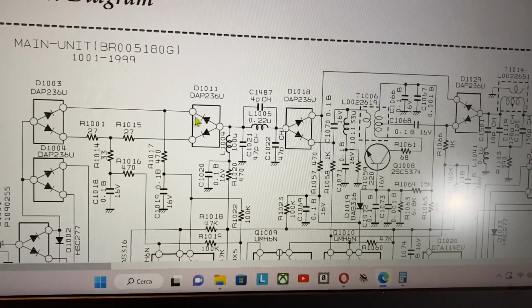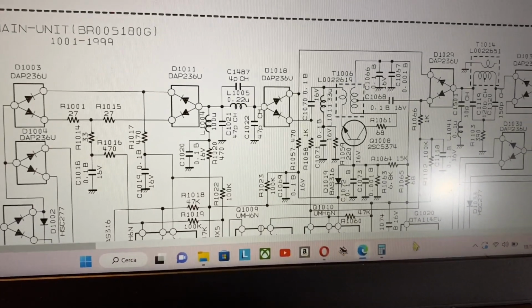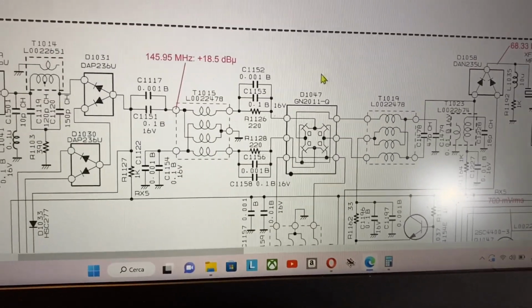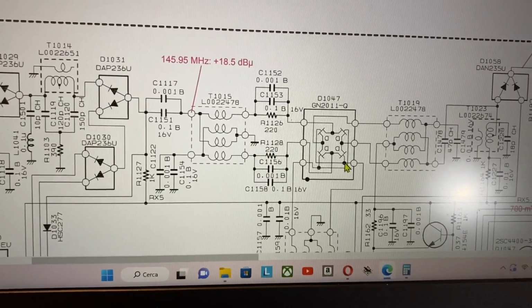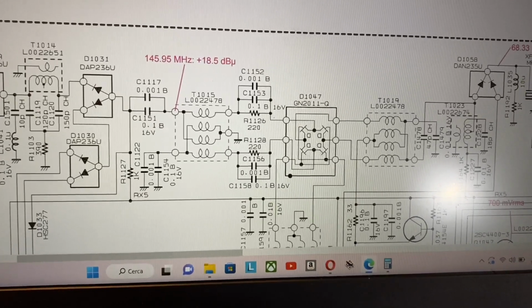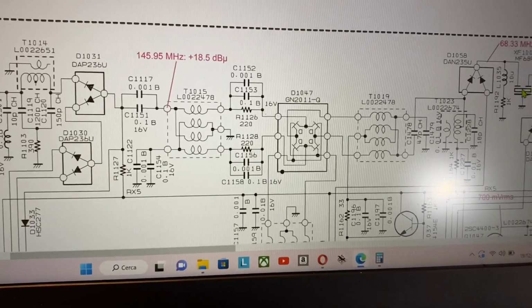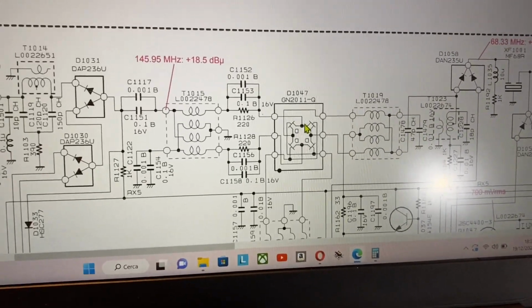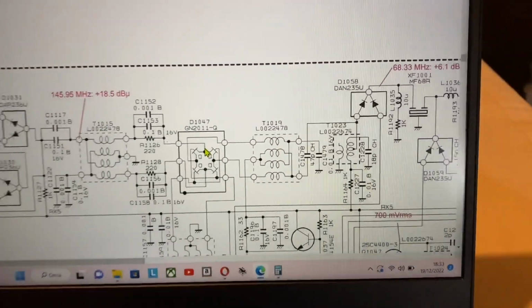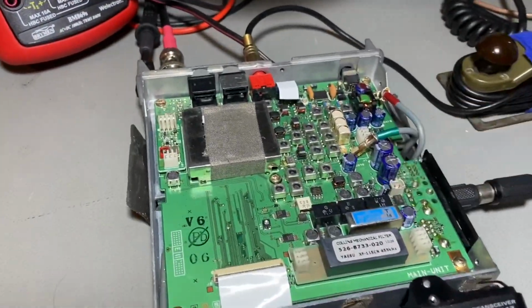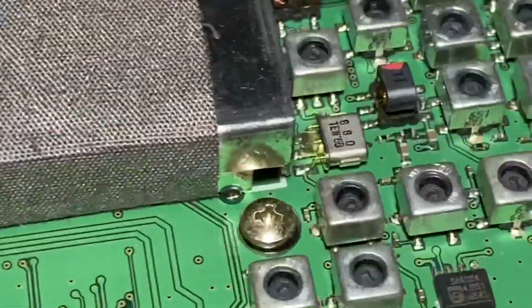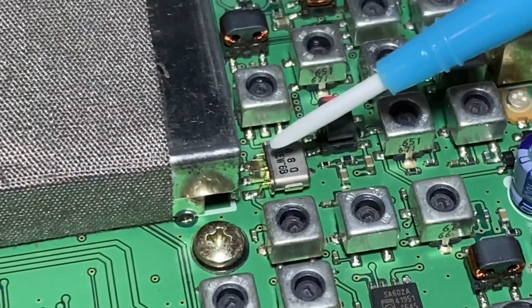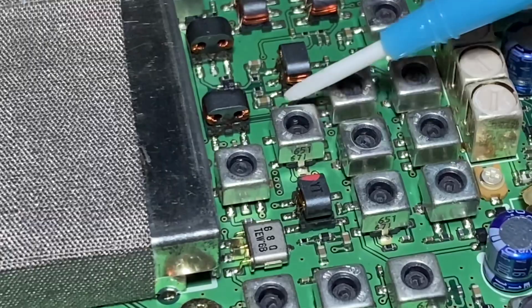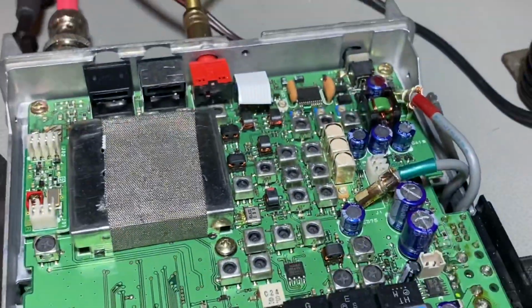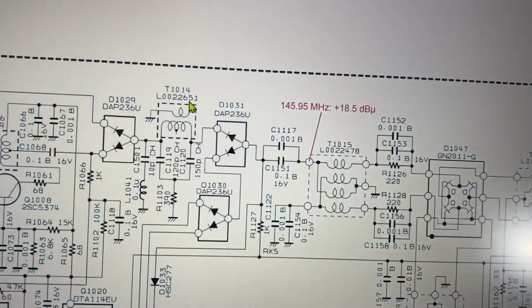So basically, if we follow along, we get into here. This is the first mixer, D1047, and then it reaches the crystal filter, XF1001, which the mixer is on the underside, on side B of the board. That's under the bottom side of the board. The crystal filter is this one here, and this is the coil T1014, which should block the 6833, and is this coil here.